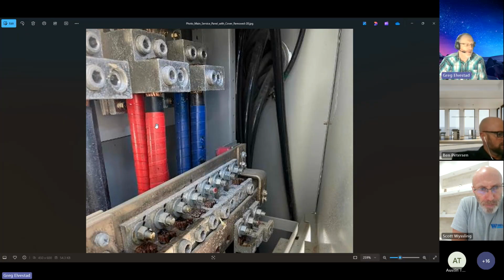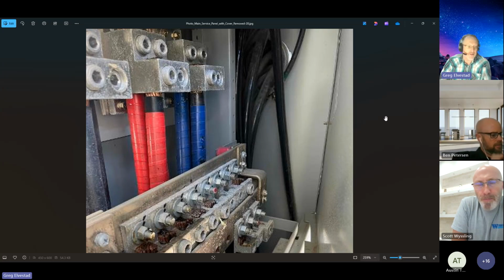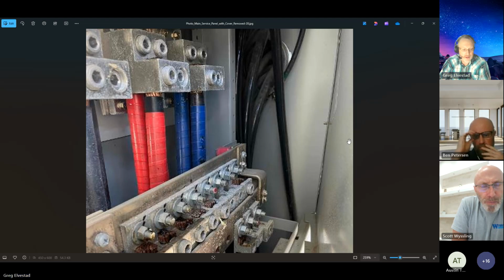This one here is likely to be 500,000 circular mils, just because it's pretty full and there's a good portion of the set screw exposed. Notice the one on the right is clearly fully seated and there's nothing in it. A little extreme, but when you look at the service panel, take a look at the set screws. It's not 100% accurate, but it's pretty good. If you see quite a bit of exposed threads, 3 or 4 threads exposed on a panel that's 200 amp rated, there's a pretty good bet that's 4/0 aluminum.